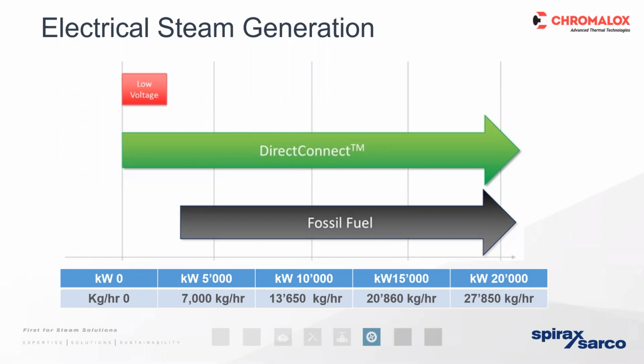So an electrical generator, well, it can be very easily incorporated into an existing steam boiler house to replace a traditional fossil fuel fired steam boiler, as it can use the same infrastructure. We can use the same pipework, and the water treatment requirements, the TDS levels permitted by the boiler, are very, very similar to a traditional steam boiler. In other words, we can use the same water treatment plant.